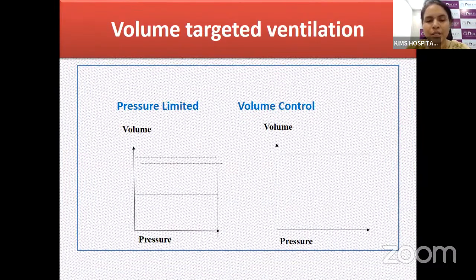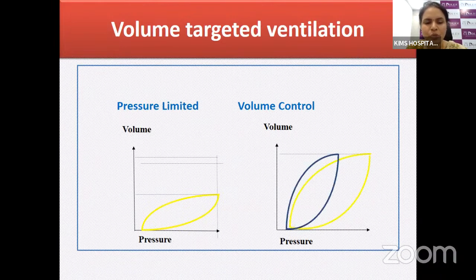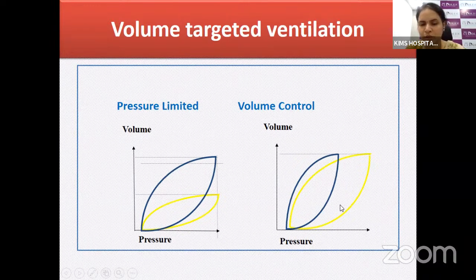Also in babies who require ventilation, wherever we have a flow sensor available and measurement of tidal volume is feasible, it is always preferable to target tidal volumes using volume targeted ventilation added to pressure controlled modes of ventilation. So we can see these two graphs here. The first graph represents a baby who is on pressure limited ventilation, wherein whenever the compliance of the baby changes with the same pressure, we get drastically different tidal volumes. Whereas when we use volume controlled ventilation, the baby's tidal volume per ventilator breath remains constant. Although the compliance of the baby changes, automatically the peak pressure is weaned off in what we call auto weaning in order to maintain stable tidal volume.